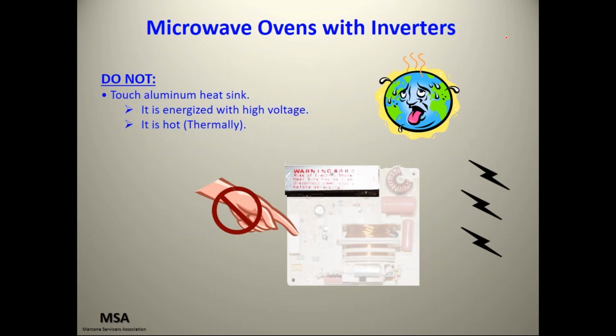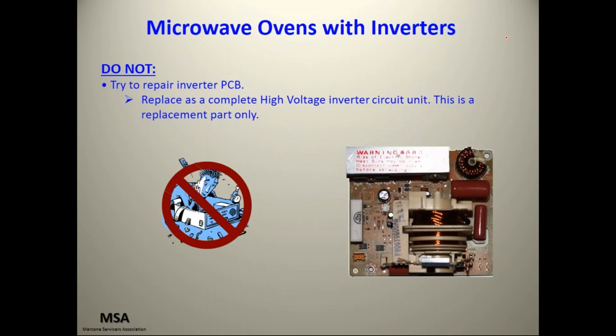And here again, they're fanatical about this heat sink. Do not touch the aluminum heat sink. It is energized with high voltage. It is hot thermally. And I know we all try to do things like this, but do not try to repair the inverter board. Replace it as a complete high voltage inverter circuit unit. This is a replacement part only. Don't try to replace the resistor or the capacitors or whatever. Replace the board. It's not worth playing around with this thing.